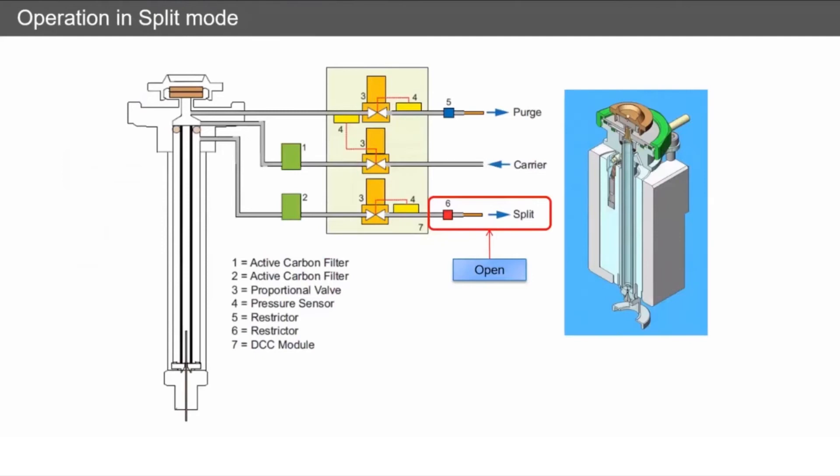Split mode. How does this work? Well, essentially it works the same way as the splitless, but the split valve is open. So our carrier flow is coming in, a portion of this is going down onto the separation column, but a large portion is going out through a split. So as our solvent expands and our compounds evaporate, a proportion of these will now be traveling out the split vent as well as going onto the column.